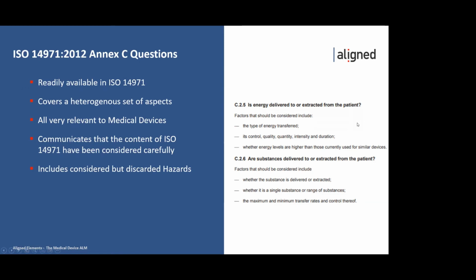Is energy delivered to or extracted from the patient? You should consider this. You know what kind of energy it is, etc. So 14971 has this list of questions. I think it's 30 plus questions. And some companies use this in their risk identification process. And the upside of this list here is that it looks very heterogeneous. So there are many different aspects, not following a very straight line.